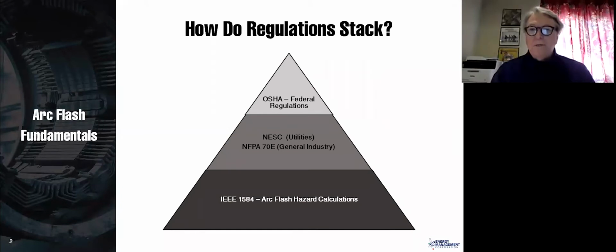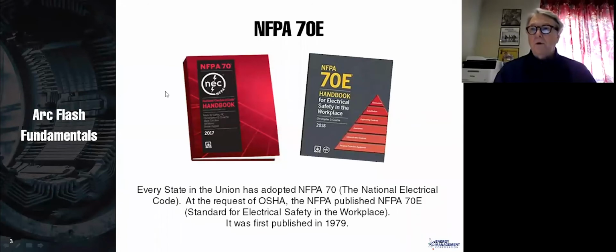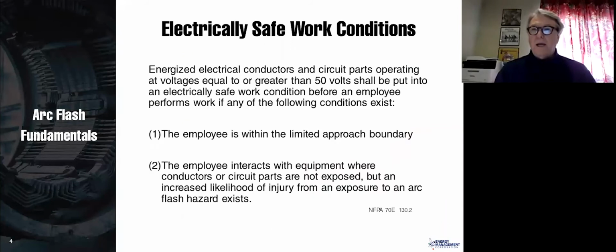These are the applicable standards, and most of the things we're going to talk about today come from NFPA 70E and IEEE 1584. As you know, NFPA 70E has the same number there as NFPA 70, the National Electrical Code. That's intentional. NFPA 70E comes out 1 year after the National Electrical Code. So the most current version of the National Electrical Code is 2020, but the one before that was 2017, and therefore the most current version of NFPA 70E is 2018.